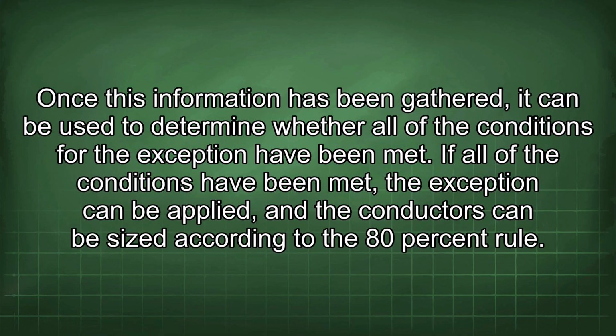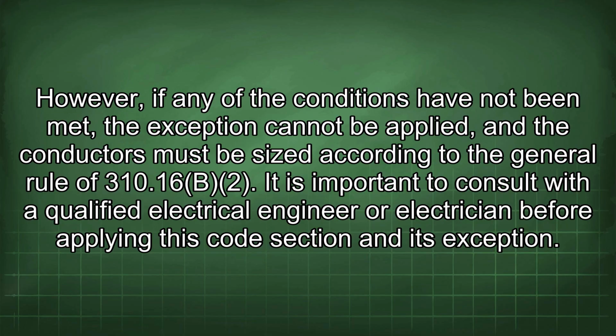Once this information has been gathered, it can be used to determine whether all of the conditions for the exception have been met. If all of the conditions have been met, the exception can be applied, and the conductors can be sized according to the 80% rule. However, if any of the conditions have not been met, the exception cannot be applied, and the conductors must be sized according to the general rule of 310.16(b)(2).